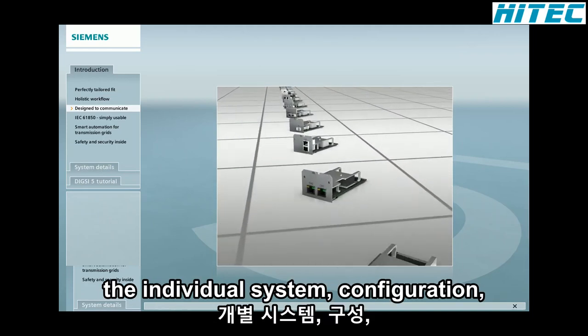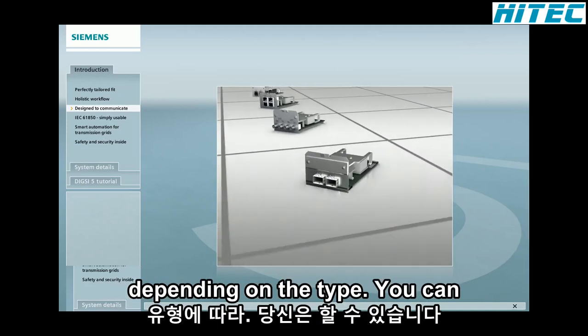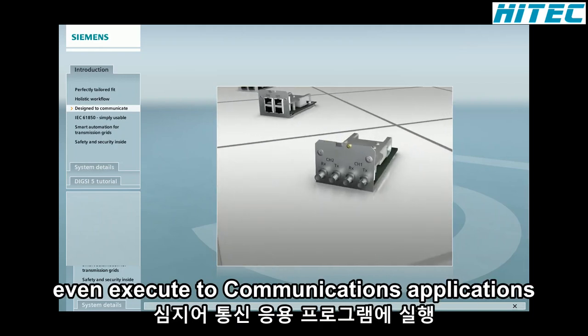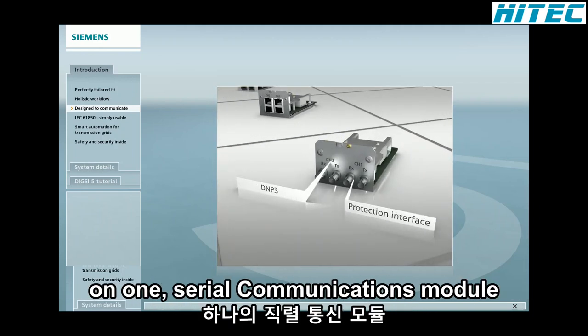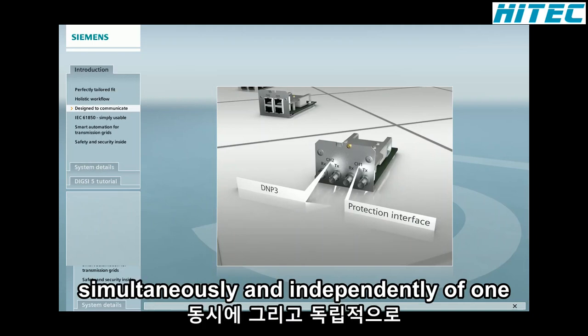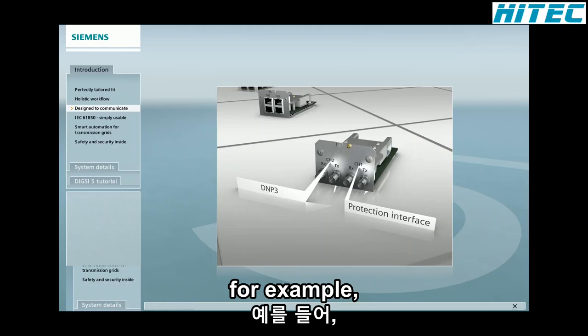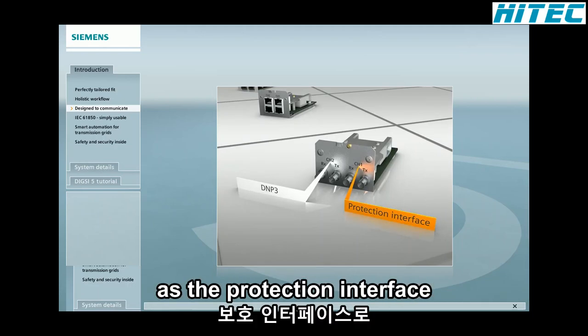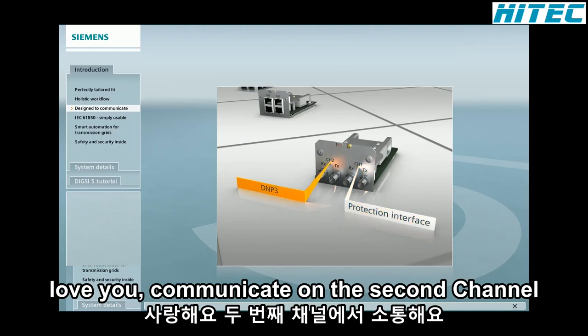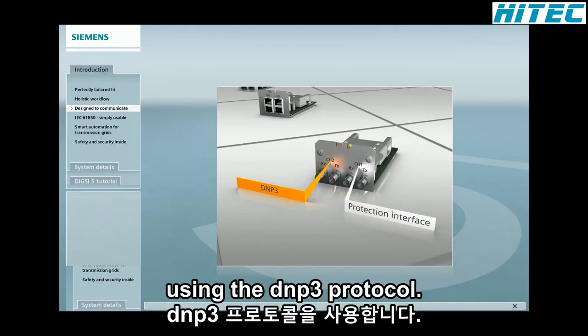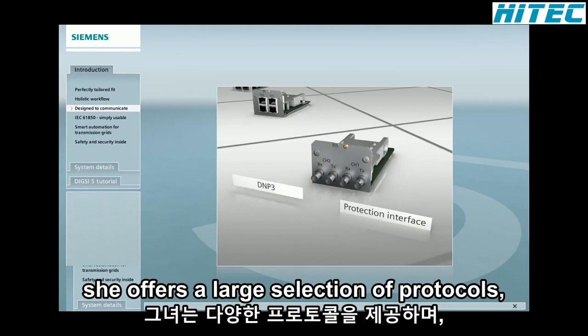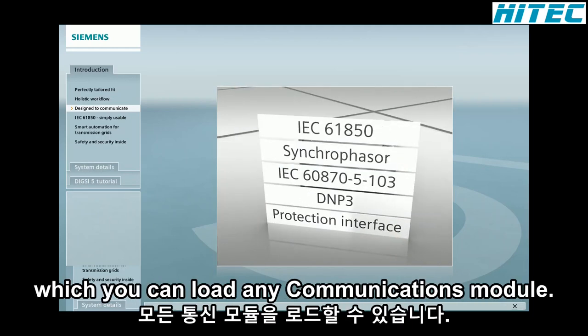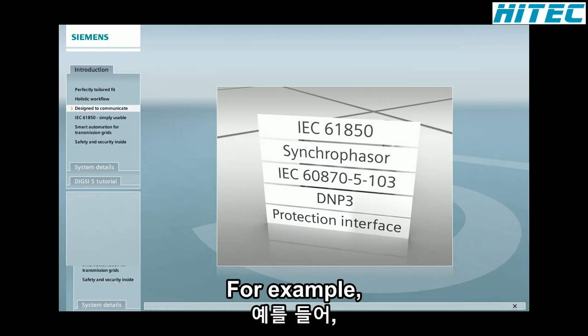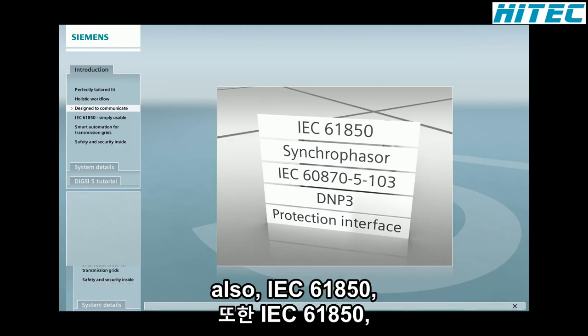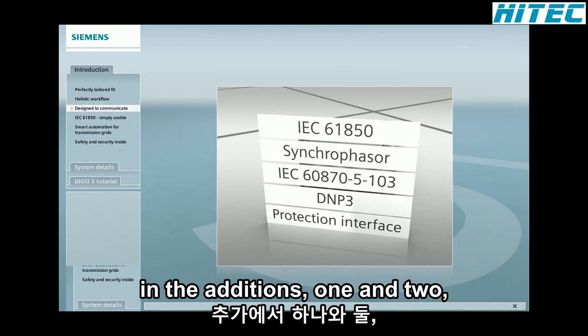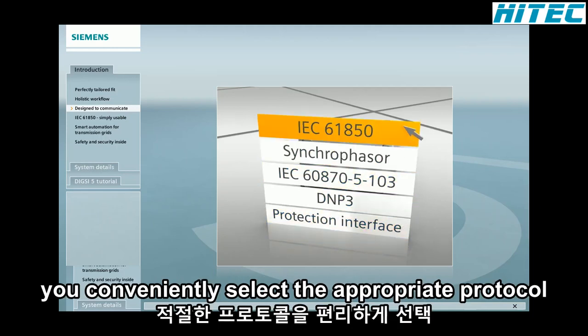the individual system configuration. Depending on the type, you can even execute 2 communications applications on one serial communications module, simultaneously and independently of one another. You could, for example, configure the first channel as the protection interface, while you communicate on the second channel using the DNP3 protocol. By the way, SIPROTEC 5 offers a large selection of protocols which you can load in a communications module. For example, also IEC 61850 in the editions 1 and 2. You conveniently select the appropriate protocol with DIGSI 5.